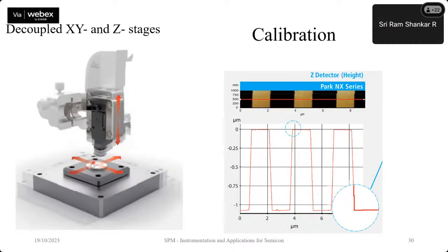Here, one advantage with this particular system is that the Z motion of the probe and the XY motion of the sample are decoupled from each other. Otherwise, there are also some tube scanners wherein you are able to make XY motion, but they also result in a cross-axis sensitivity with respect to Z motion.